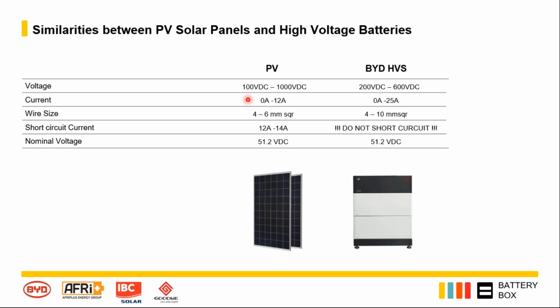With regards to current, your current on your PV strings is typically between 0 and 12 amps, and your current on your BYD HVS tower is anywhere between 0 and 25. They are fairly similar. It's also quite a lot of similarity in your wire sizes that you use. Your solar strings typically use 4 to 6 solar cable, and for your HVS, you can also use between 4 and 10 square millimeters. For your HVS, because it's only rated at 25 amps, and your Gen24 inverters only have 22 amps on the battery input, you wouldn't need to go above 6 square cable.